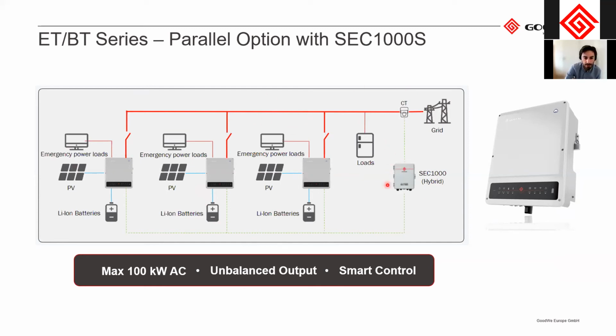So here you see the master unit or the control box. Here are your loads connected. Here is the grid. So the loads here get power from all inverters connected in parallel. Each inverter, however, needs to have its own PV system connected. So each inverter has 2 MPPTs, and there you connect your PV system. And each inverter also has its own battery. When the grid is on, the inverters are optimized so that they work as a single system, so to say. However, when the grid is disconnected, you see the switch here, then each inverter will operate as a single, isolated system.